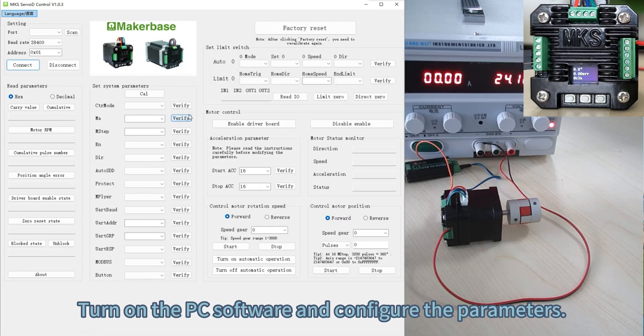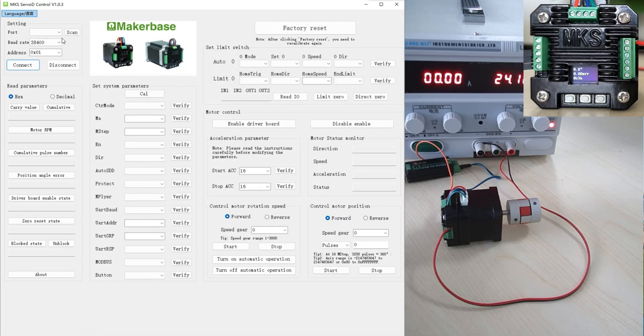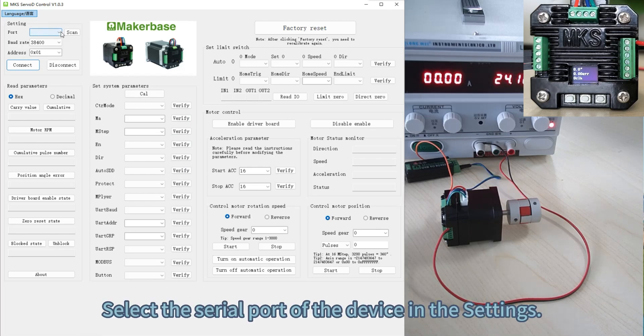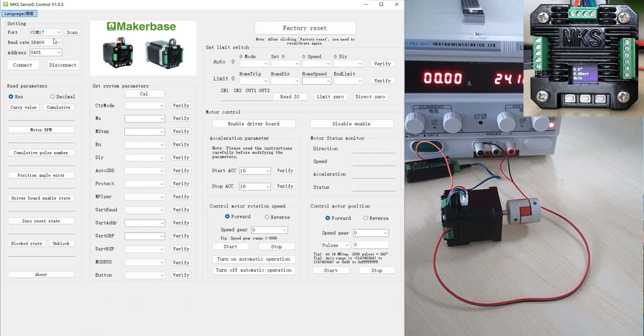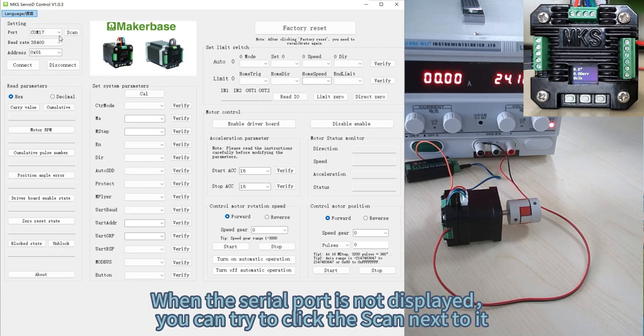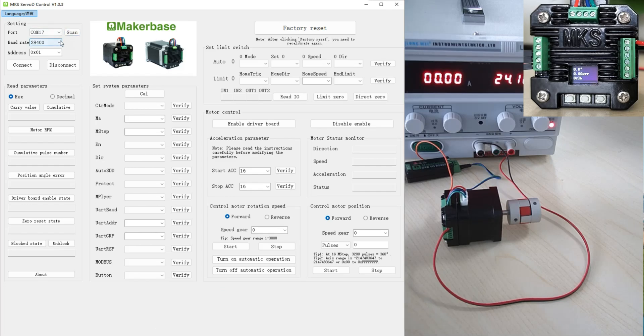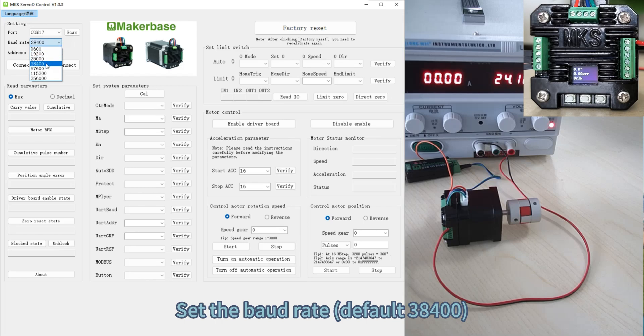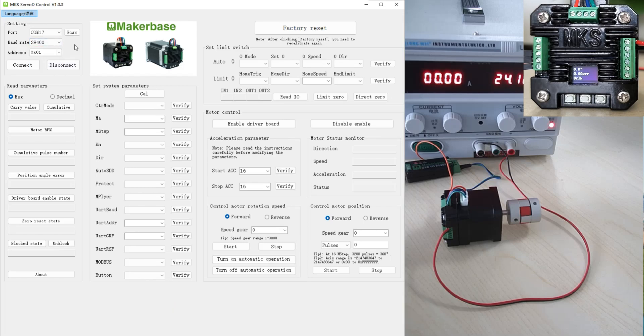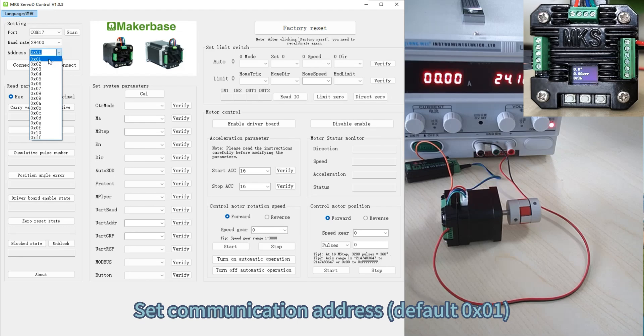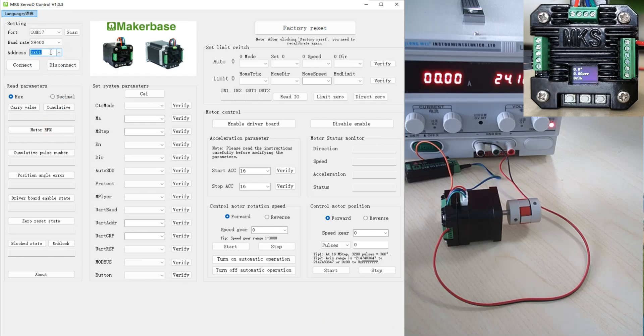Turn on the PC software and configure the parameters. Select the serial port of the device in the settings. When the serial port is not displayed, you can try clicking the refresh key next to it. Set the baud rate to the default 38,400 and set the communication address to default 0x01. Click Connect.